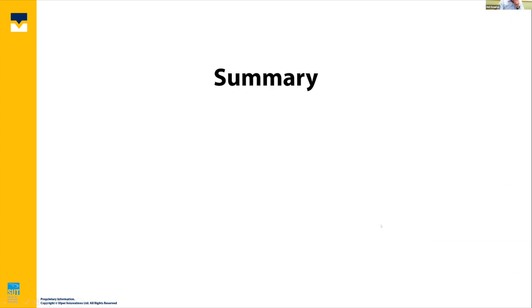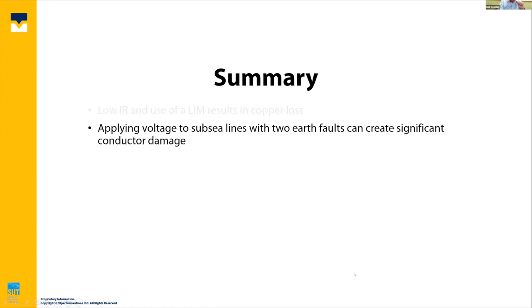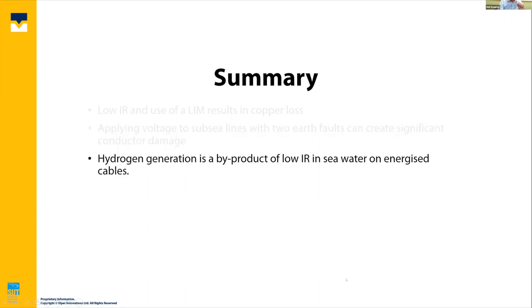So, my summary slide: low insulation resistance and use of a line insulation monitor or IMD will result in copper loss. Applying a voltage to two subsea lines with two earth faults can create significant conductor damage, and not just significant, but generally rapid conductor damage. Hydrogen generation is a byproduct of low IR and seawater on energized cables. Now, interestingly, there are a lot of theories running around that hydrogen being generated within the umbilicals, maybe from corrosion of the steel wire armor, is somehow getting into the cable and causing low IR, i.e. it's hydrogen that causes low IR.